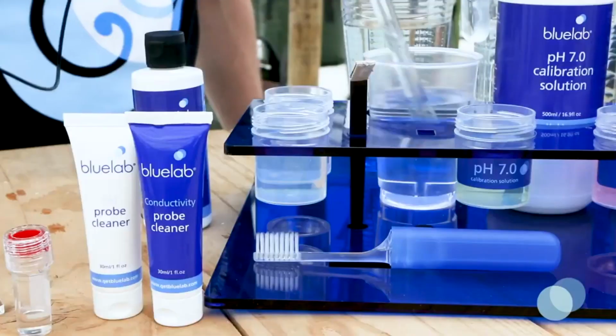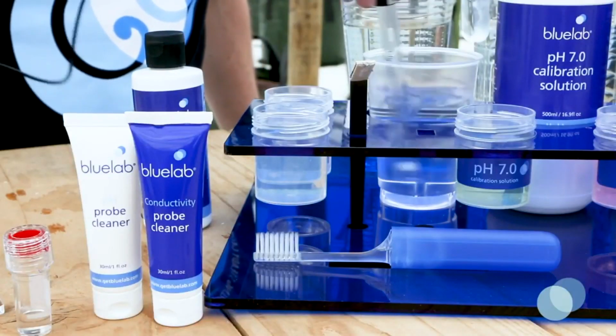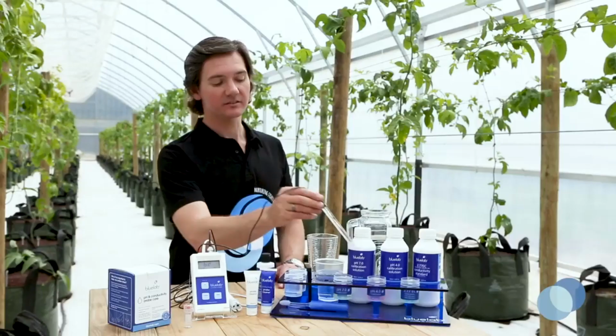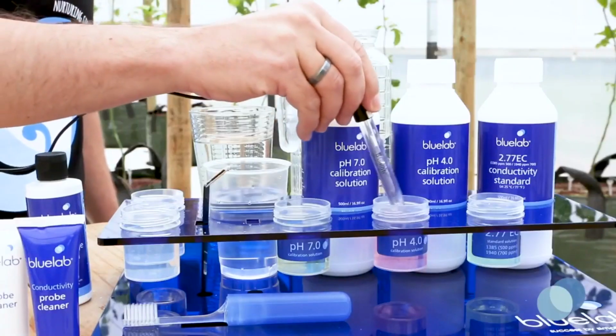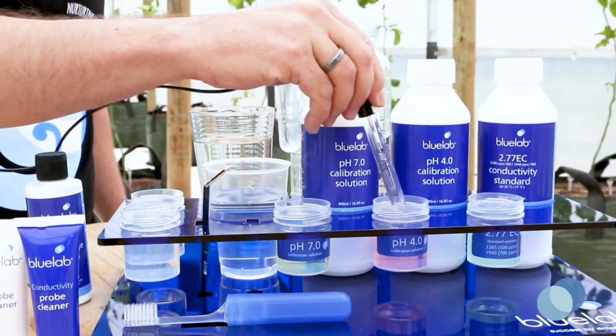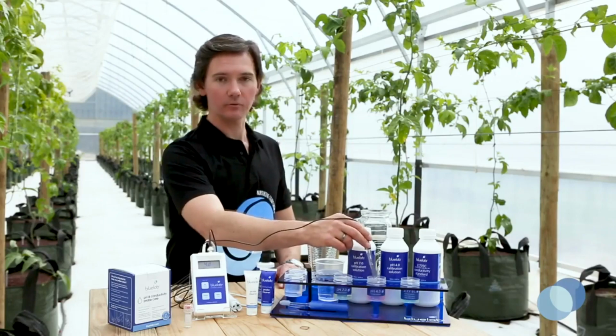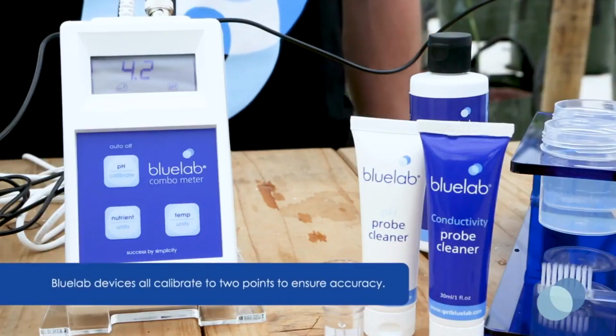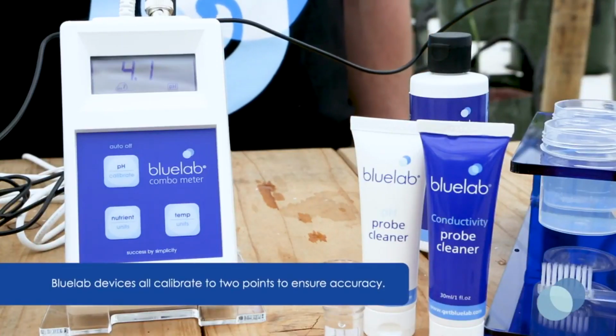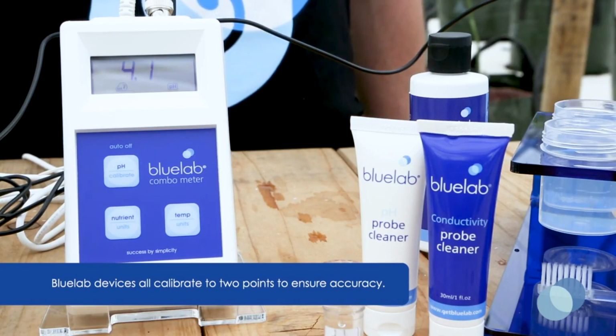Next, rinse the probe in fresh, clean tap water. Next, place the probe in fresh pH 4 calibration solution. Remember to give it a good swirl to ensure you've got good contact between the probe glass and the calibration solution. Wait for the reading to stabilize on the combo meter.